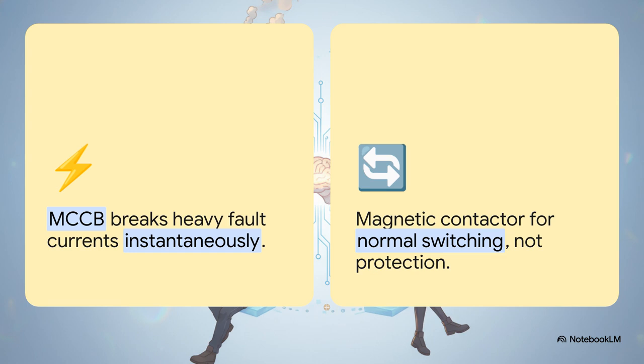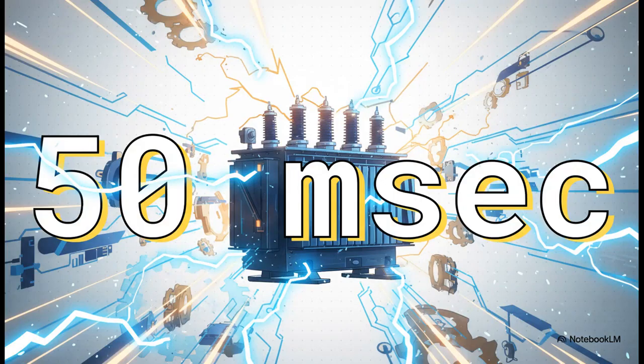The magnetic contactor is explicitly not a protective device. For protection, you need the MCCB, the molded case circuit breaker. The MCCB is your ultimate failsafe against catastrophic short circuits, featuring adjustable magnetic pickup settings that kick in the moment the current spikes to 5 or 10 times the normal levels. And in these situations, speed is literally everything.